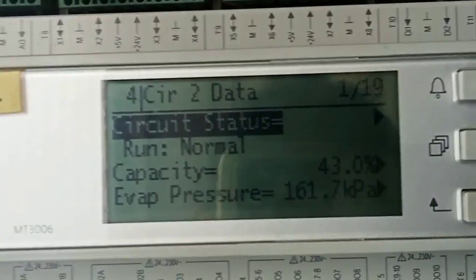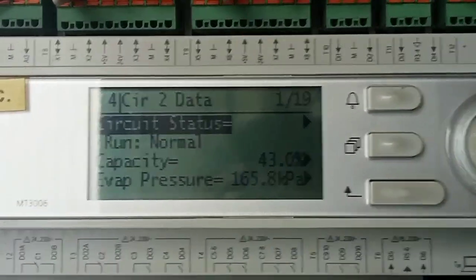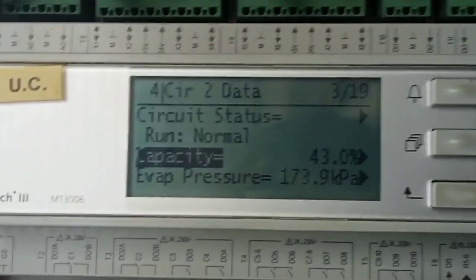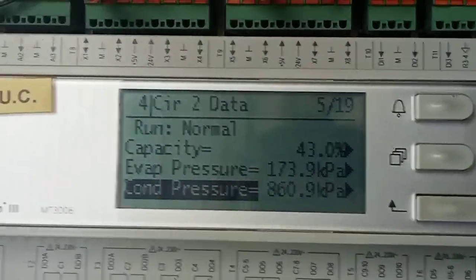Now see the chiller status also. Now see the chiller status, it's running normal. Everything now can be checked here. This one, how much capacity? 43%, evaporator pressure, condenser pressure.